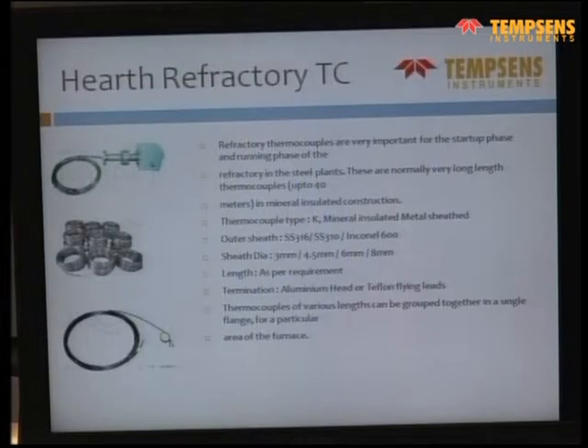Yes, output is individual. For some GTRE, we did a thermocouple in which they made all the thermocouples parallel. If you make the thermocouples parallel, then it will give you the average temperature. So we have also supplied that. In this case they want individual temperature, but one particular customer wanted average temperature, so you can make it parallel to give the average temperature. Can we see that particular product tomorrow? We can check if it is lying there. It is a simple product. It's MI cable, but one MI cable roll is for 3 meters, another may be 6 meters, another 10 meters, and they are all connected in a junction box with multiple terminals.